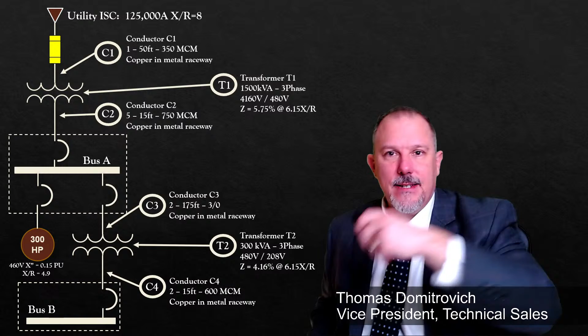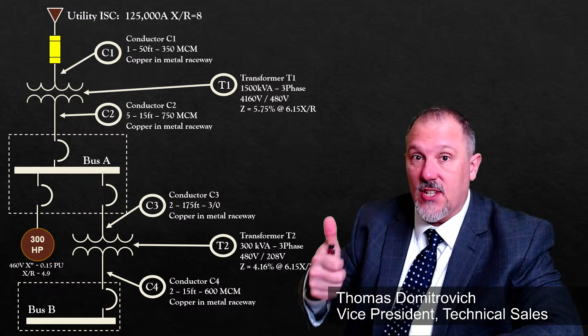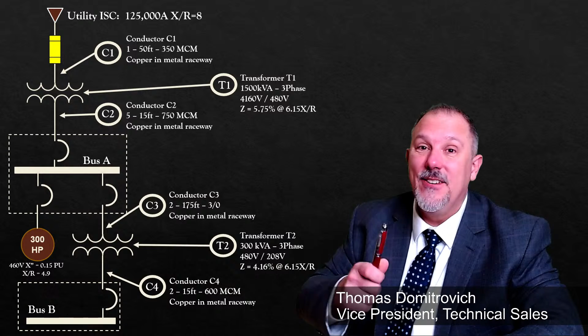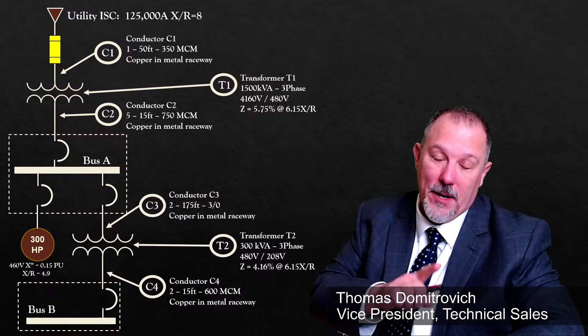I've got two transformers for this. We picked the primary fuse and the primary circuit breaker, but we're going to have to make adjustments to our conductors, increasing the size, which will probably increase our fault currents downstream. But on the secondary of this transformer, not that much - you should have already learned that from one of my earlier sessions.